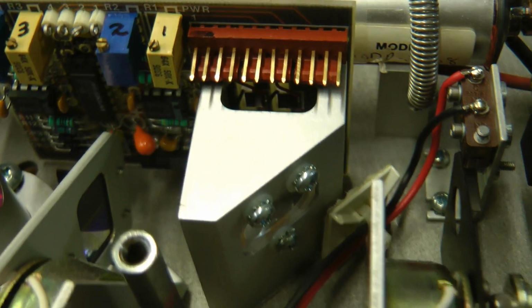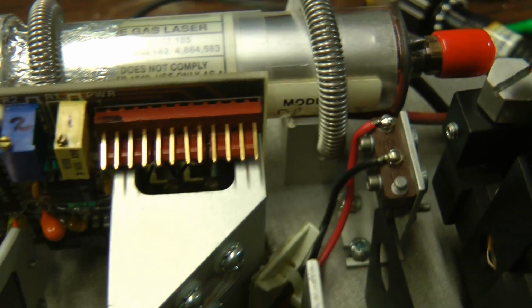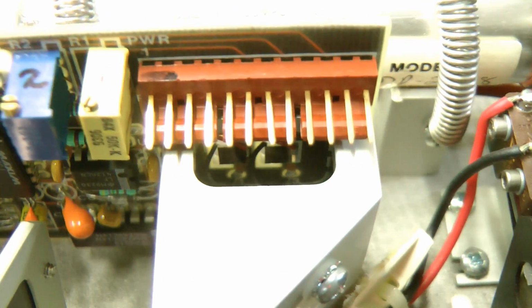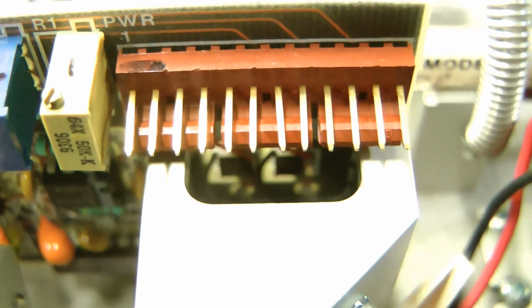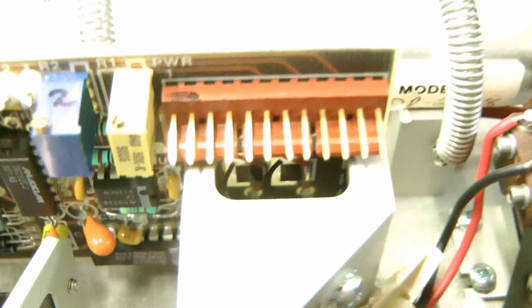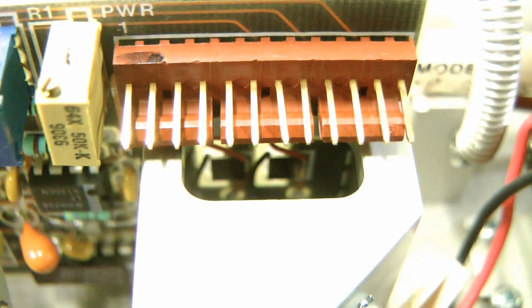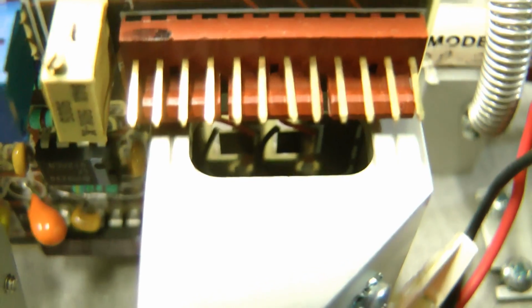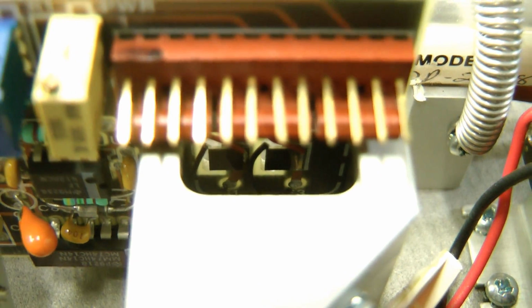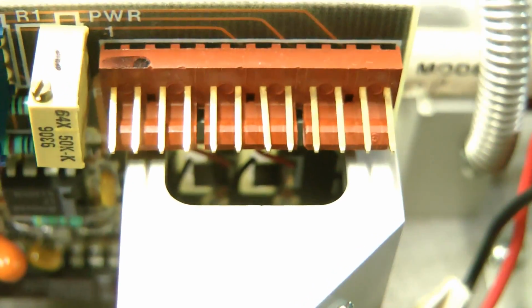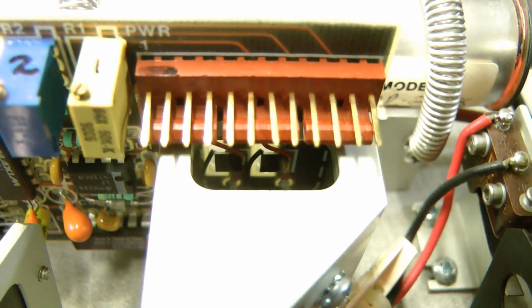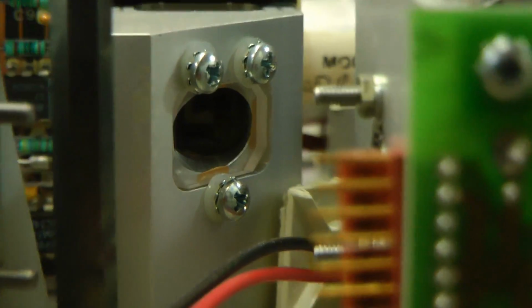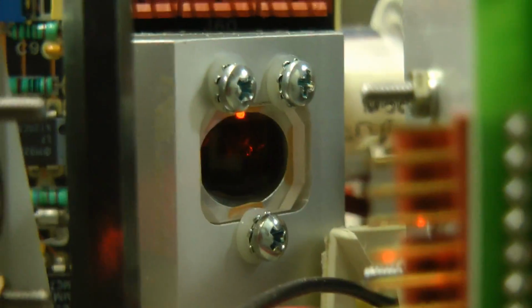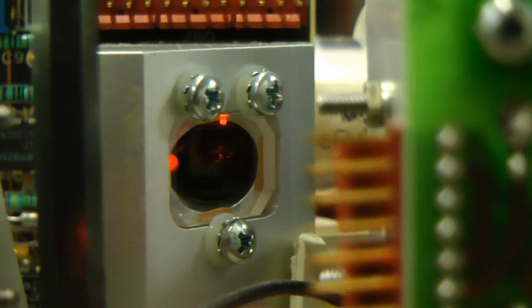There's a power measurement in here. Let me see if I can show you those. If you look down in there, you can see these bare die photodiodes. It looks like they literally just solder wires straight onto the die. There we go. That should be a slightly more in focus image now. Yeah, odd style of photodiode. And if you look down in here, if I turn the aiming beam back on, you can just about see the aiming beam hitting the photodiode.